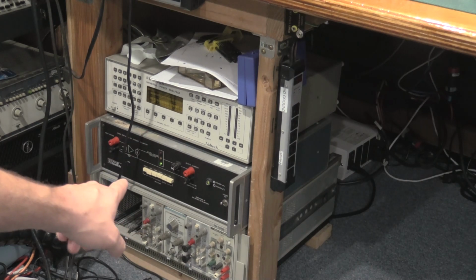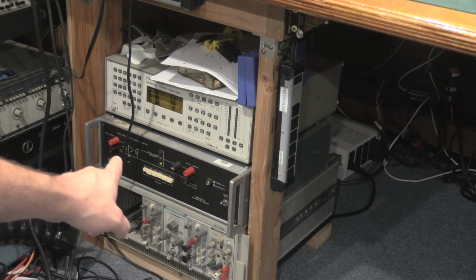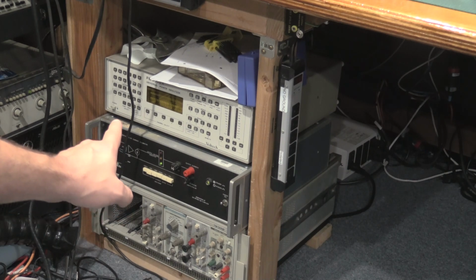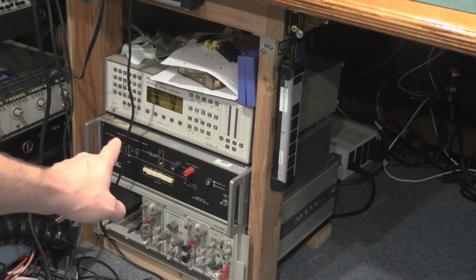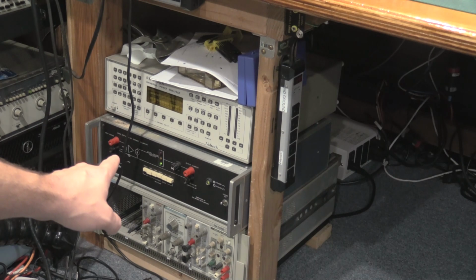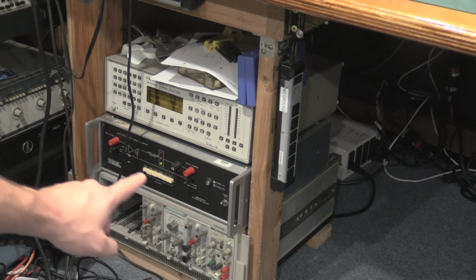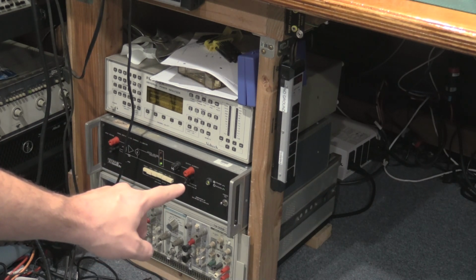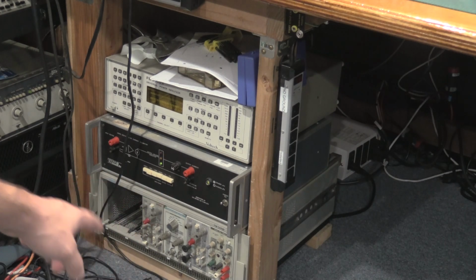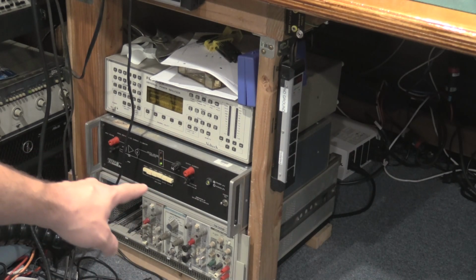It'll be 2 volts for this particular one. So it's a 10 volt. It is a 10 volt input. So whatever voltage is put on these 2 pins, current comes out on these 2 pins, depending on what these switches are set to. So we'll set it to the 10 amp range, which is its highest range.